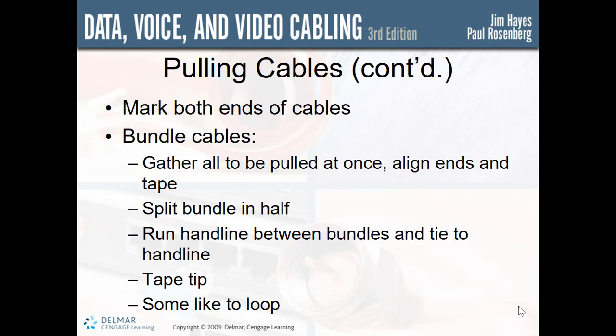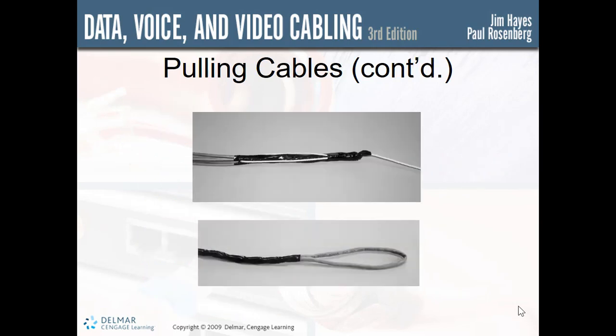So we have cable 1 in the work area goes to port 1 in the closet. Cable 2 in the work area goes to port 2 in the closet. Put all of our cables together and then try to pull them all at once if you can. That is the most efficient way to do it. Run a hand line between the bundles and tie your hand line to your tape, and then you're off and running.